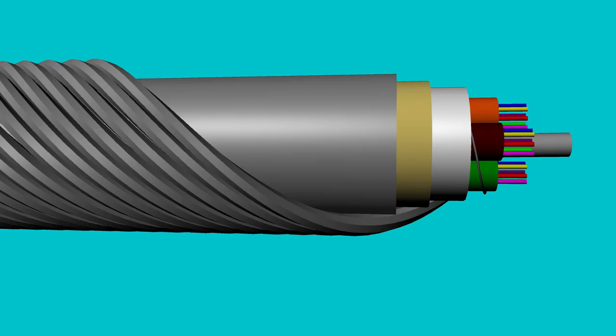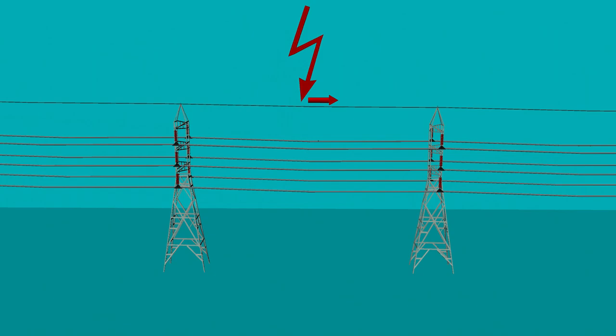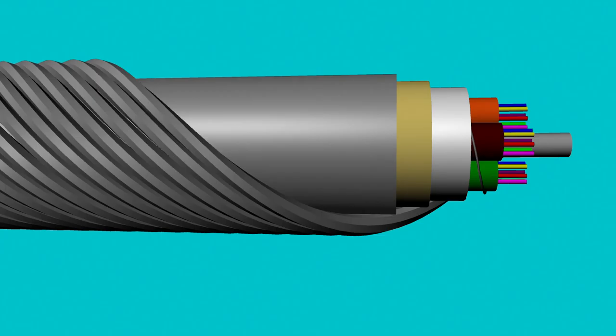The tube is then covered with either aluminum strands or aluminum clad steel strands. The number of these strands vary according to the requirements. Normally there are 11 steel strands in OPGW. These aluminum or aluminum clad steel strands are good conductors of electricity and provide protection to the phase wires in case of lightning strokes by passing the surge voltages to the ground.